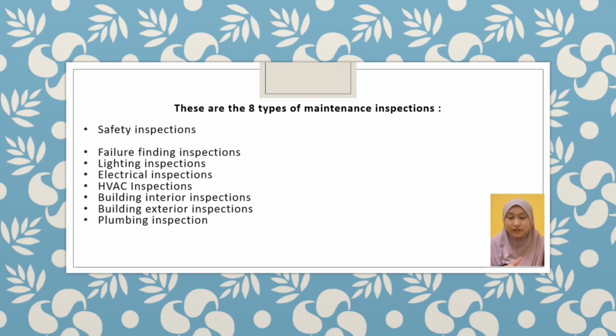Next, failure finding inspections. These inspections check the operation of devices or protective devices that cannot be readily checked unless the primary system fails. Failure instances must be simulated to test these components of equipment or machinery. Next, lighting inspections. Bulbs should be checked regularly and replaced in a group when they begin to fail for efficiency. In addition, the technician should examine controls, filters and baffles on transformer systems as well as cables, hardware and gaskets on exterior lights. Then, electrical inspections.